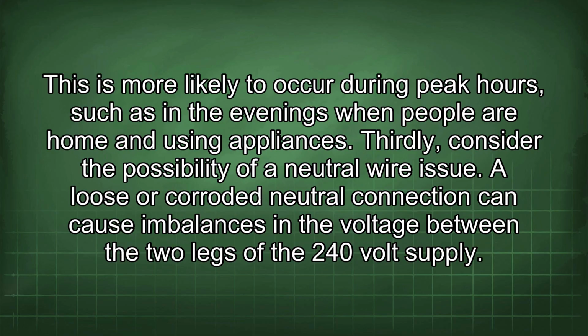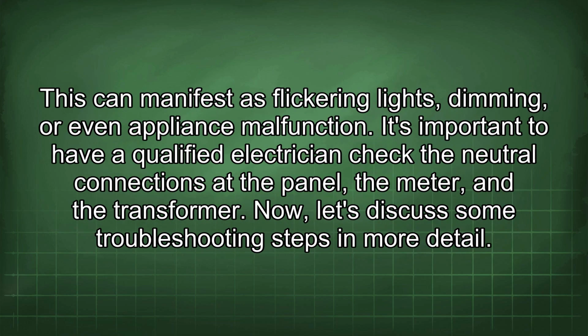This is more likely to occur during peak hours, such as in the evenings when people are home and using appliances. Thirdly, consider the possibility of a neutral wire issue. A loose or corroded neutral connection can cause imbalances in the voltage between the two legs of the 240 volt supply. This can manifest as flickering lights, dimming, or even appliance malfunction. It's important to have a qualified electrician check the neutral connections at the panel, the meter, and the transformer.